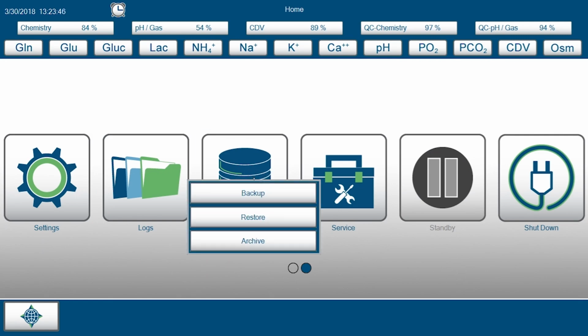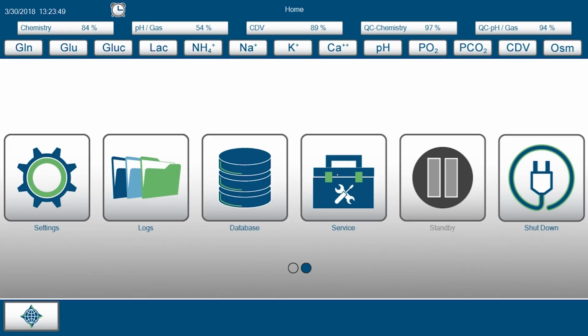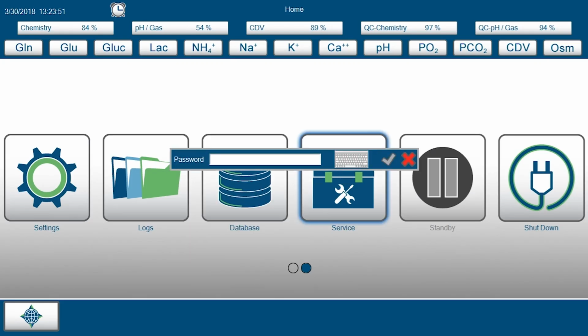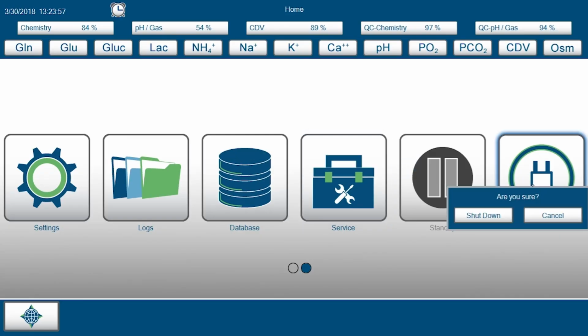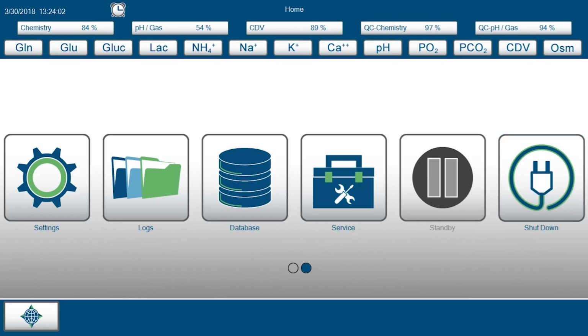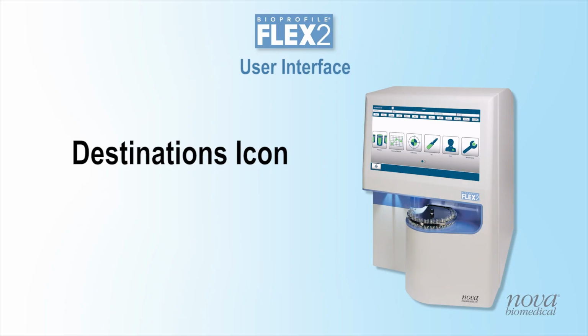The Database menu allows you to back up or restore the database. When using this function, the database is backed up to and restored from the internal bridge computer. The Service menu is only for Nova-trained service and support personnel and cannot be accessed by any end user. The Standby icon is not currently available, but will be available in later releases of Flex 2 software. The Shutdown icon will turn off the analyzer, host computer, and internal bridge computer. If you plan to keep the analyzer off for more than 72 hours, you should perform a long-term shutdown. This procedure is outlined in the Maintenance module of this training.